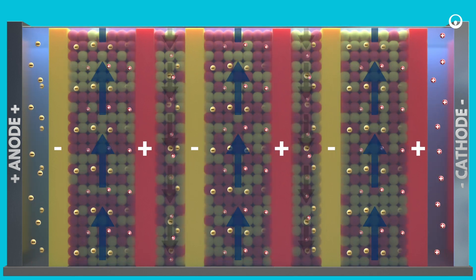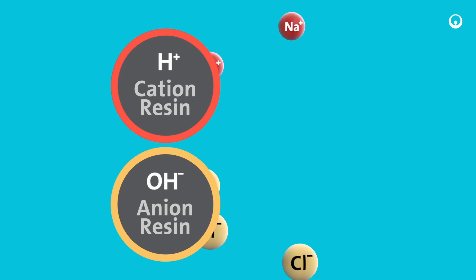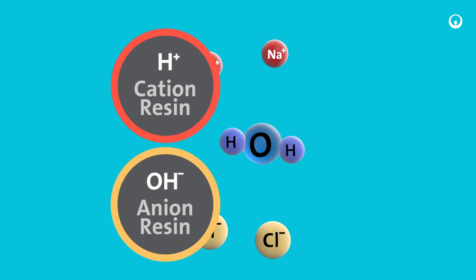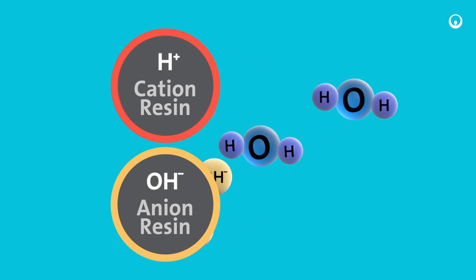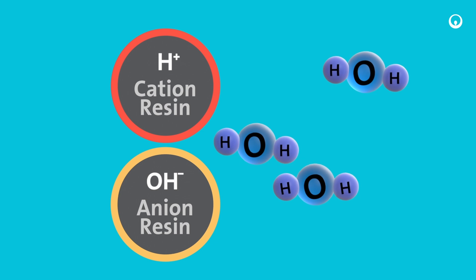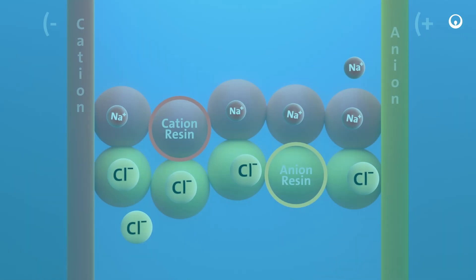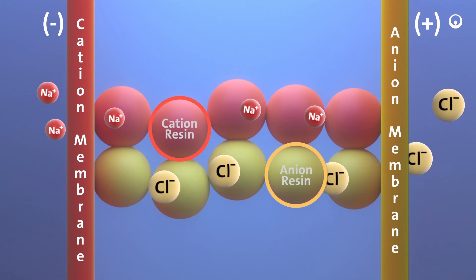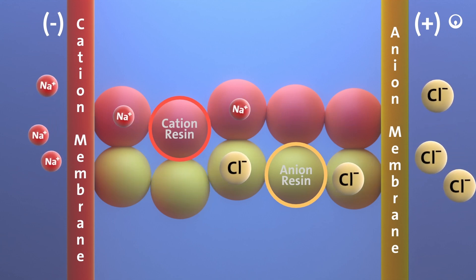With both anion and cation ion exchange resin added to the dilute compartments, ion exchange occurs as per usual kinetic and thermodynamic factors. As the resin picks up ions, hydrogen and hydroxide ions exchanged from the resin combine to form H2O. Ions in the ion exchange resin migrate toward the electrodes, through ion exchange membranes, and into concentrate chambers.